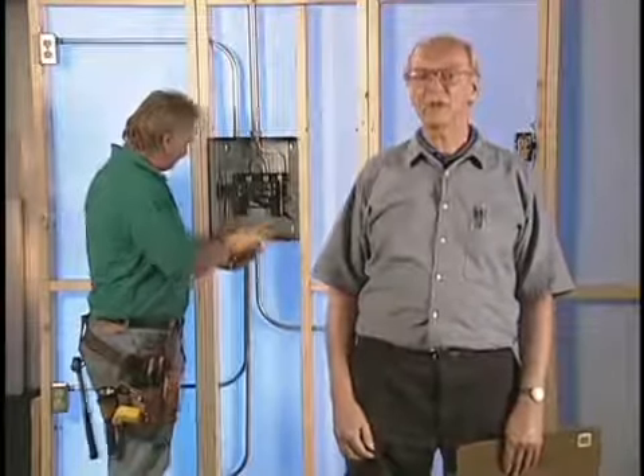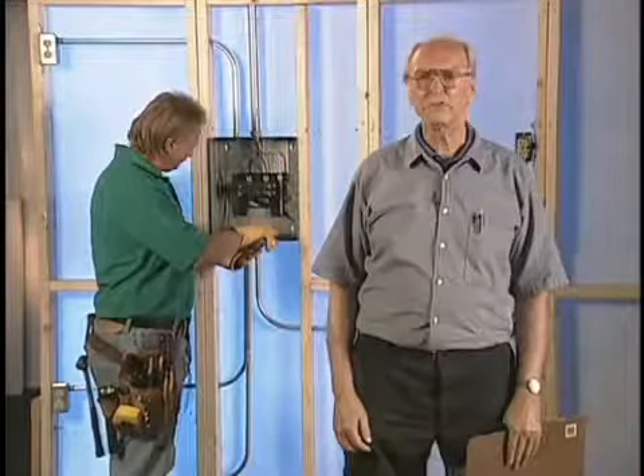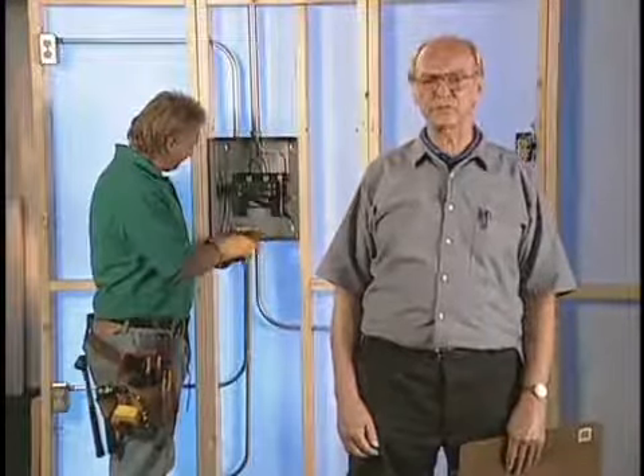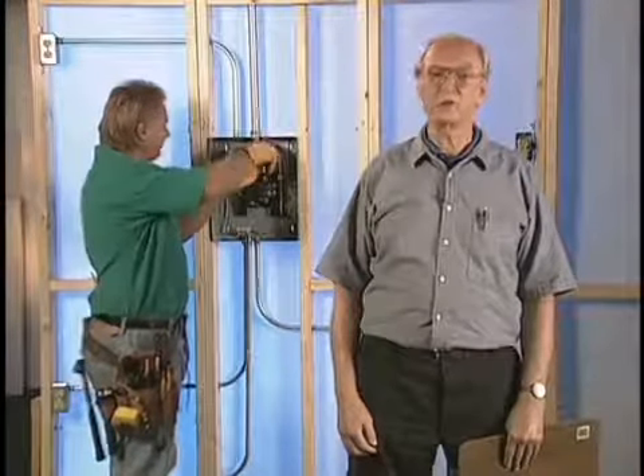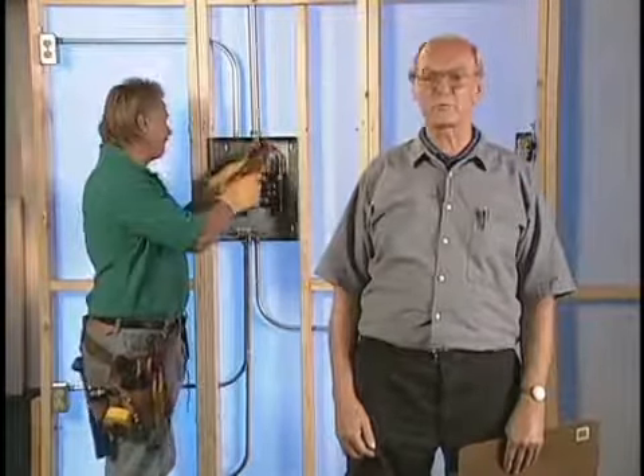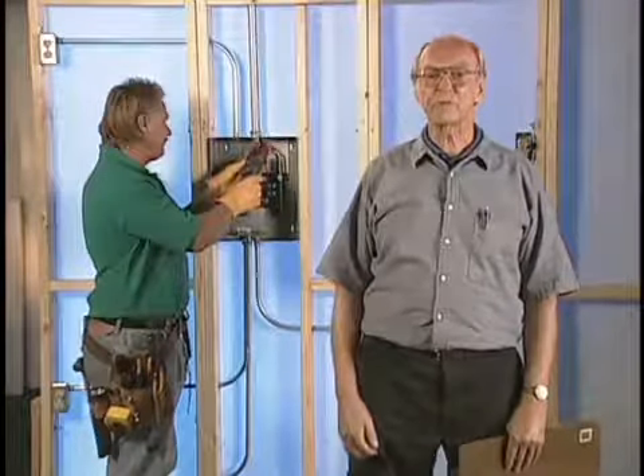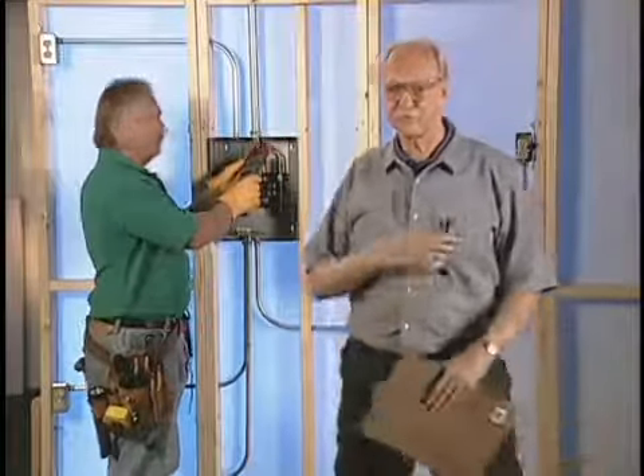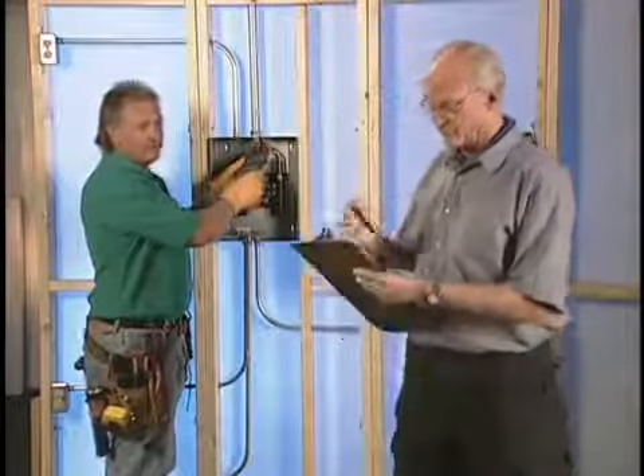Now we begin the net current search. First, check the panel feed conductors for net current using a large-jawed clamp-on ammeter. If there is a net current, record it. 4 amps.